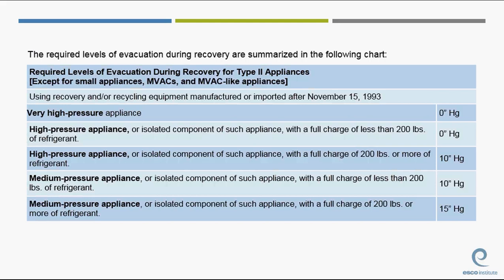0 inches of mercury. What is that? What type of pressure is that? Vacuum. It's inches of mercury column. Yeah, but 0. Am I in a vacuum or am I just at standard pressures? Isn't that almost a perfect vacuum? Anybody have a gauge in front of you? No. 29.9 inches of mercury is as low as my gauge goes. If you look at your low pressure gauge, you'll see that 0 inches of mercury and 0 psig are at the same spot.